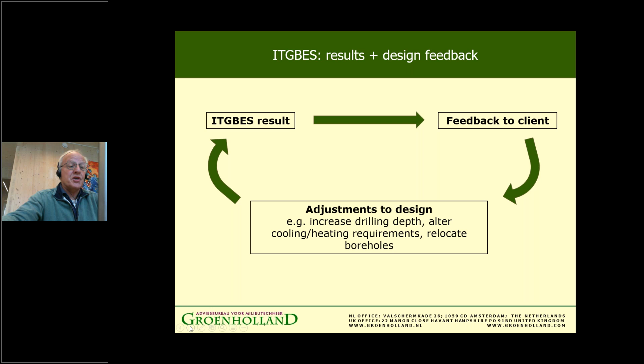You can increase drilling depth. Yeah, that will give you a lower extraction rate per meter. You can alter the cooling or heating requirements. It means you can do more regeneration, do more cooling, or put a solar thermal panel on your roof and put heating back into the ground. Or you can relocate your boreholes, because obviously a lot of the interference will also depend on the positions of the boreholes that you have. So with that result, you can go back to your design and improve your design.